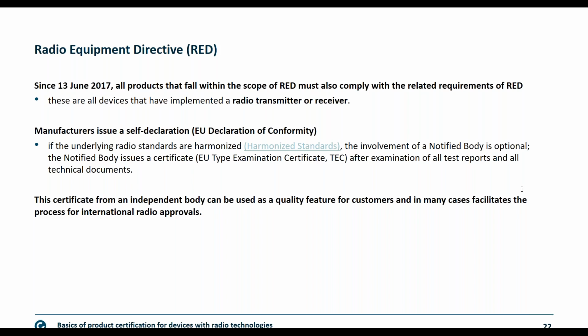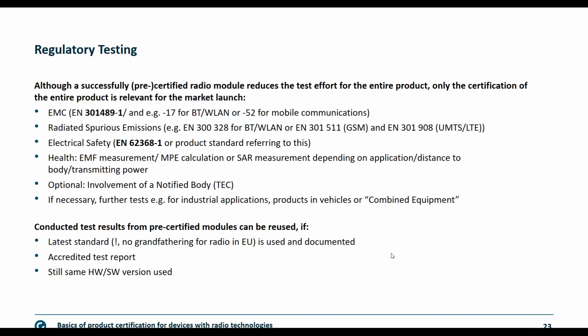In general, if you're using harmonized standards and use a notified body on top, this is to be seen as an added value. This is kind of a quality feature. This is an additional certificate of quality for your device. Let's go through regulatory testing in a very short view. Sometimes we get to know that distributors, and mainly distributors, tell customers that as long as they're using a pre-certified module, they do not have to do any testing afterwards. So these are rumors we have seen many times, have heard many times, and they still continue in the market. A pre-certified module is always a good story, and it helps you shorten your development process and your regulatory approval process, but this does not mean we do not have to test anything afterwards.